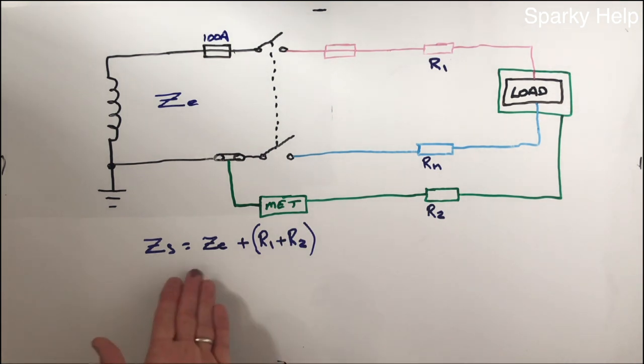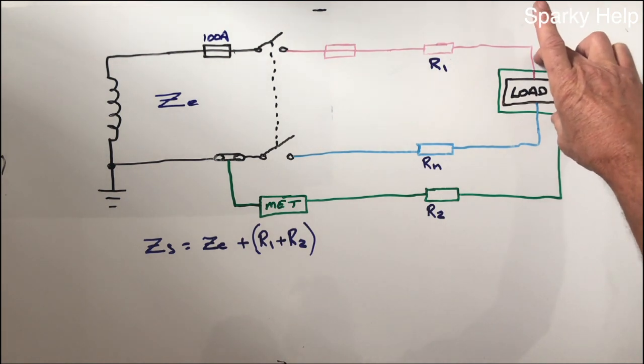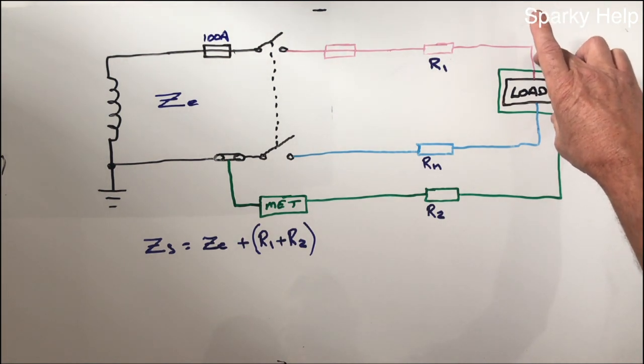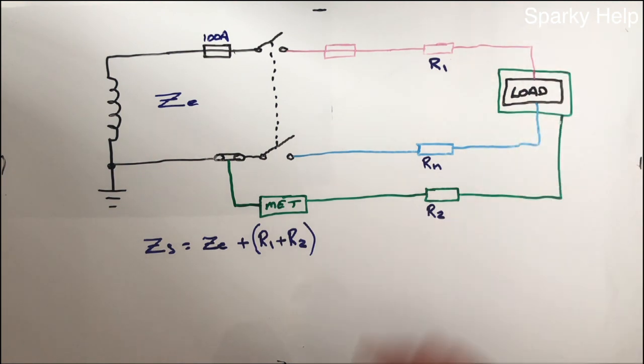ZS is what we know is made up of, ZS equals ZE plus R1 and R2. Remember ZS is a measurement at the extreme of every circuit, so at the furthest point of every circuit, because it's the highest resistance for every circuit.